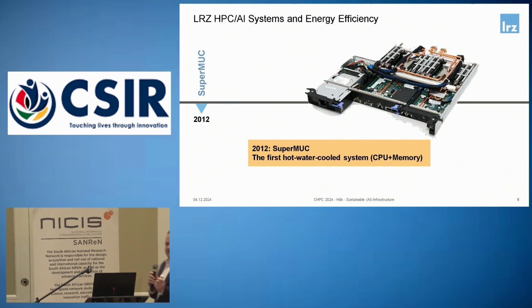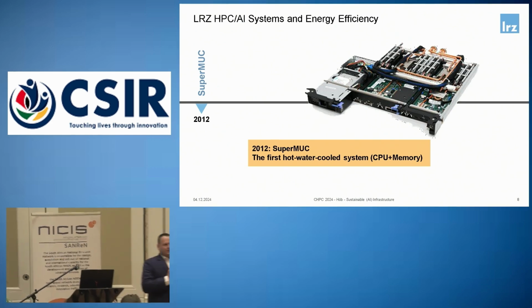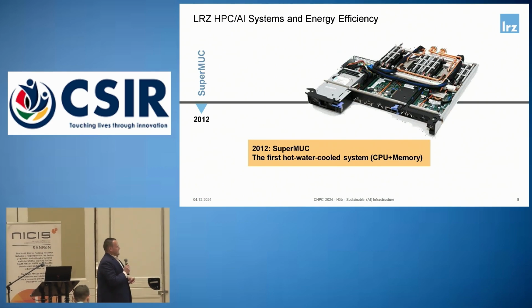What is the benefit of a hot water cooled system? Well, in our latest system we go in with an inlet temperature of 42 to 43 degrees Celsius to cool the processors, the memory, and all the other parts. We come out at 54 to 55 degrees Celsius, so a plus of 10 degrees.